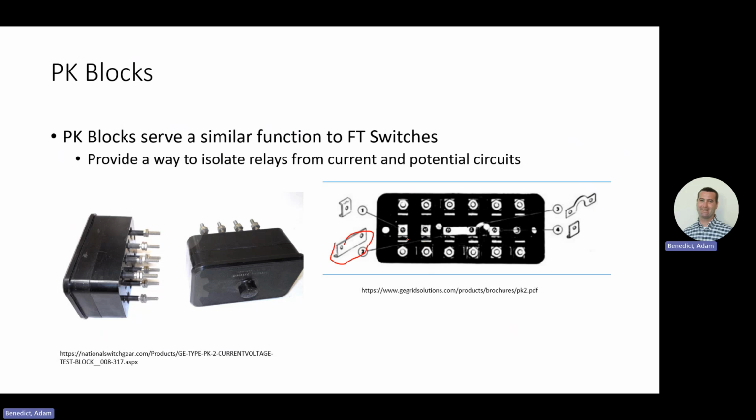So you want to be looking to make sure those are installed in the right sets. And then basically this is mechanically operated. So as you pull that out, this little bar goes up, makes contact with this and this instantaneously, super fast, and shorts it out.